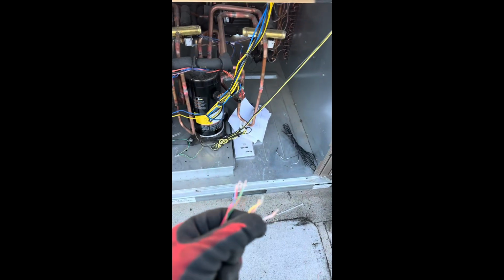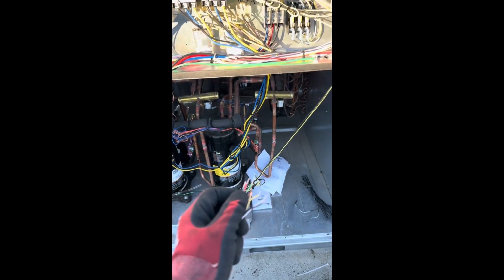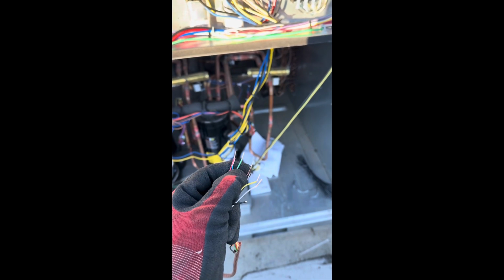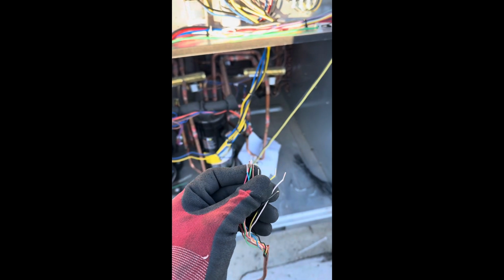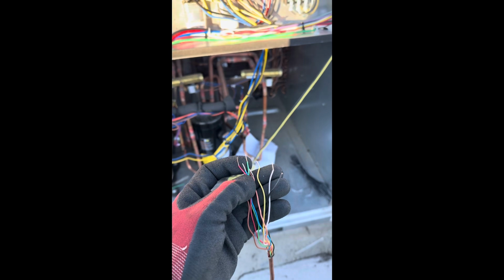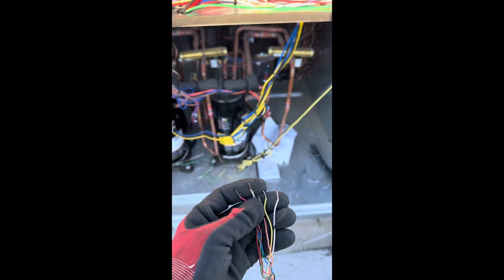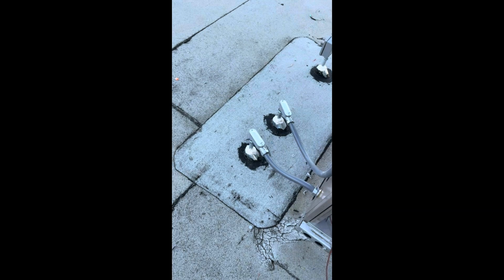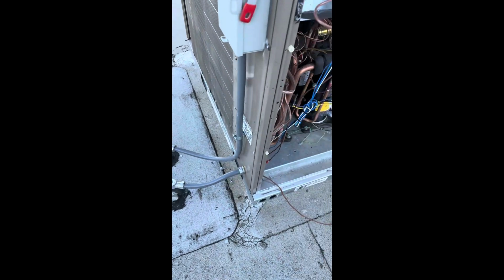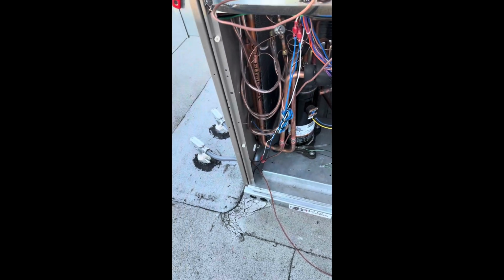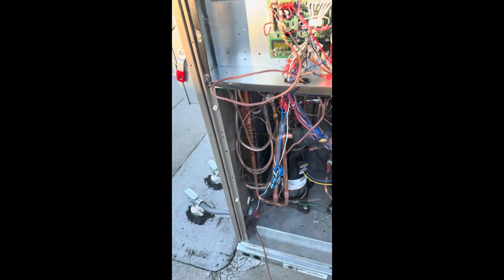And what's happening is I am getting continuity between this black wire, your red wire, your common, and then your Y1, and I believe it was also between Y2. Not too sure on that, but either way, we still have quite a bit of shorts on here. More than likely we got a short with a strip through this MC. So we're gonna either try to find the short and repair it, or we're just gonna run a new line since this is a new project. So we're gonna come back and follow up on that one.